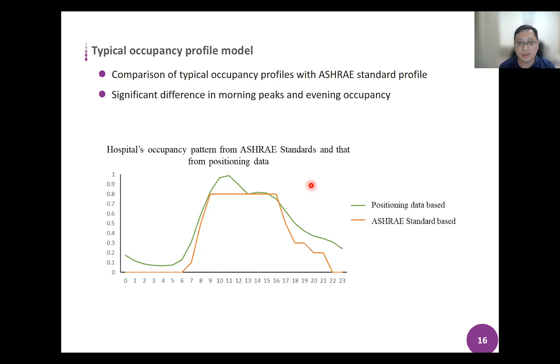Comparing our generated pattern with the current ASHRAE standard, we can see the typical pattern is very different, especially for the hospital occupancy pattern. There's a very significant difference at midnight, where there's still around 10-20% of people inside the hospital, and the peak load at lunchtime is even higher than the standard pattern. That drives differences in building design and sizing issues.